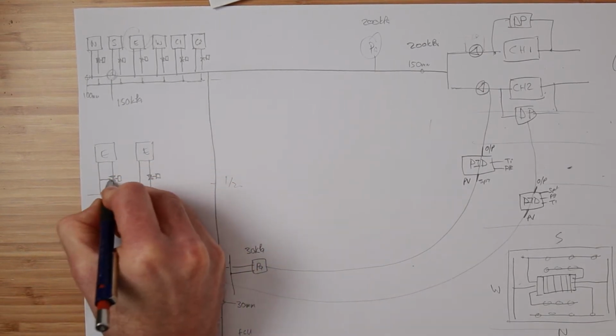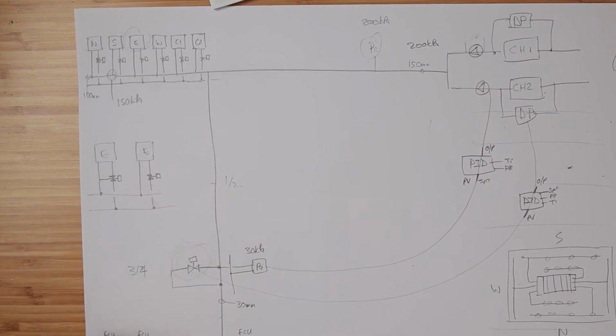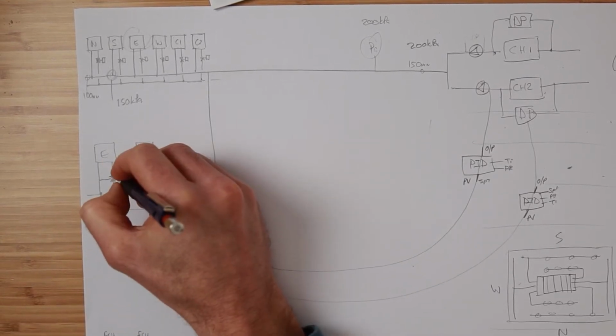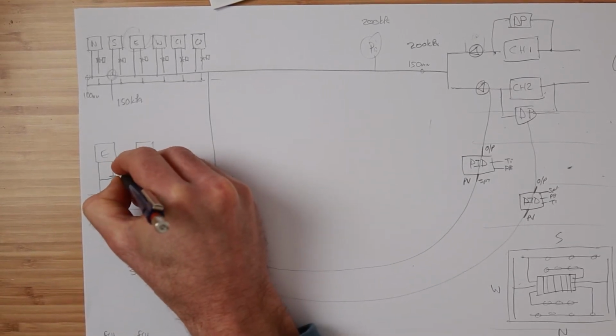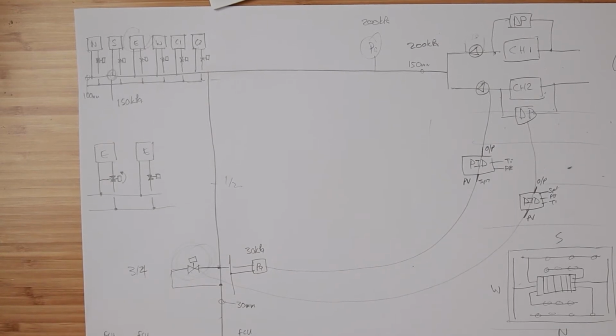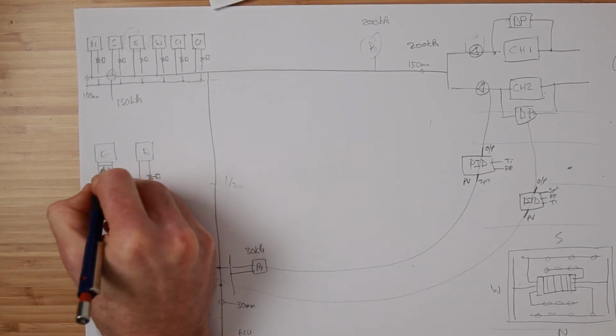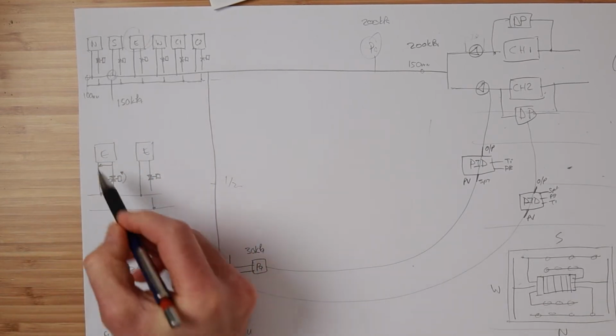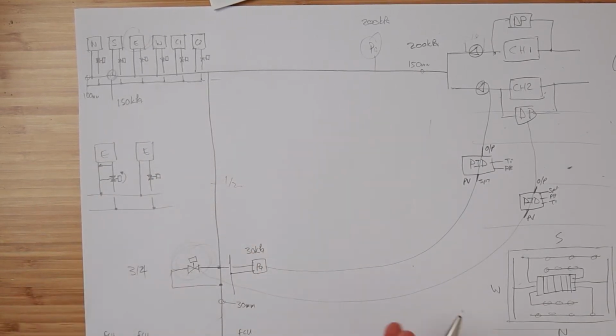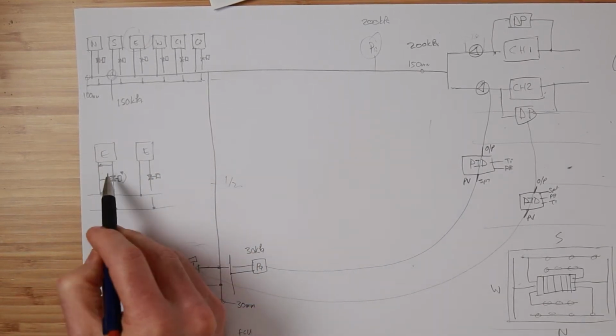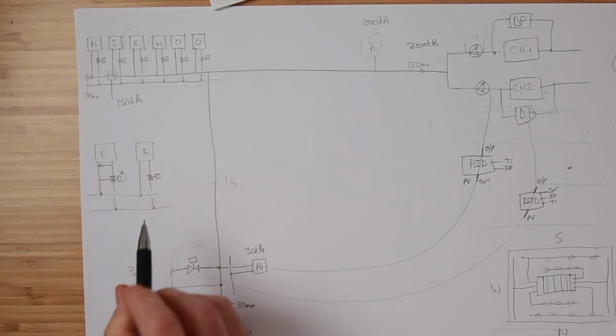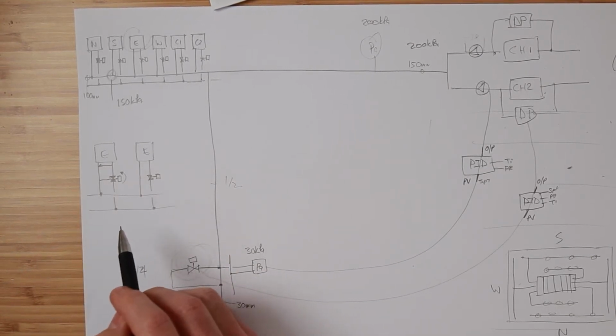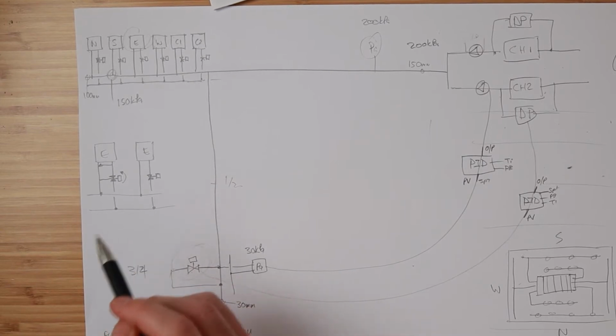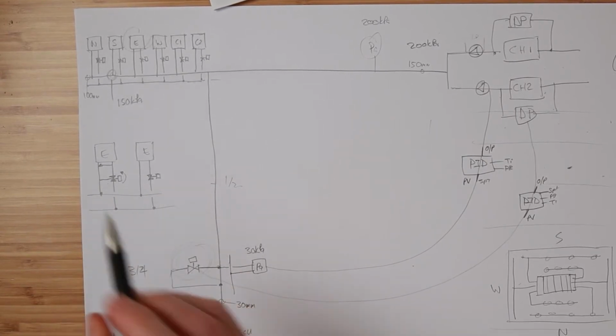Now, with a three-port system, like we had a very long time ago, the valve authority formula only requires the pressure drop across the fully open control valve, and the formula requires the pressure drop across the coil. Now we have those pressures, and we discussed this I think in detail, I can't remember, in those other videos. We need to know this, but with a two-port system, the valve authority equation is not the same as the valve authority equation of the three-port system.